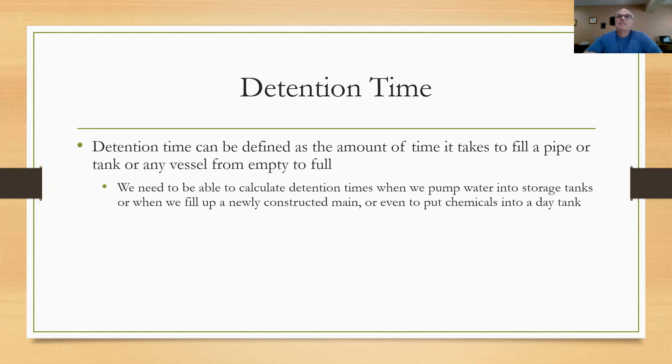So detention time, we can define it as the amount of time it takes to fill a pipe or an elevated tank, or we can define it as the time it takes to empty something from totally full to totally empty. In other words, we need to know how long that operation takes. Detention time calculations will tell us. We need to be able to calculate detention times when we pump water into storage tanks or newly constructed mains, put chemicals in a day tank. And when we do that, we always use this detention time formula. Detention time always equals the volume divided by the flow rate.